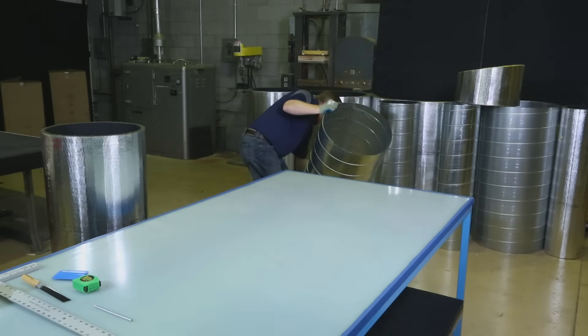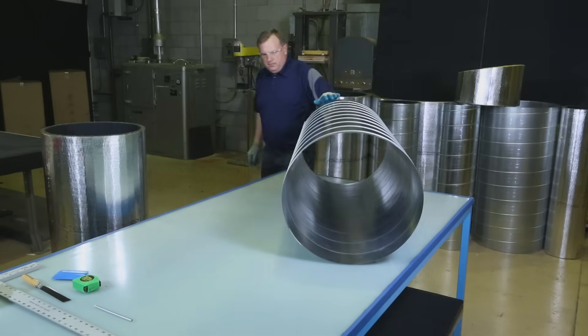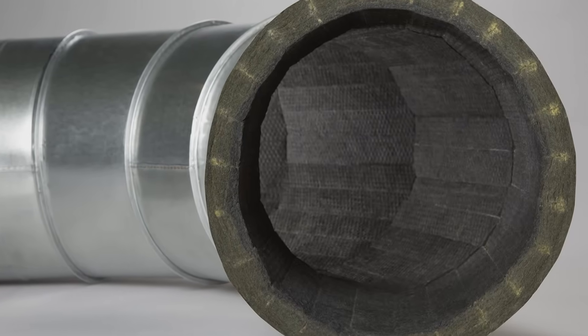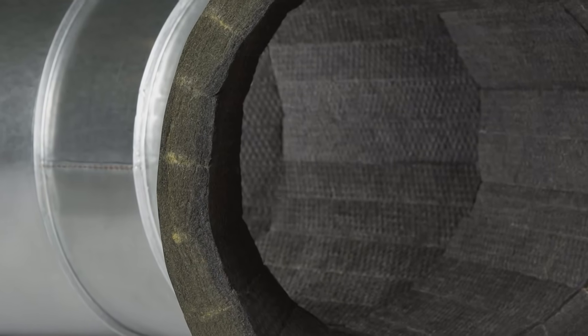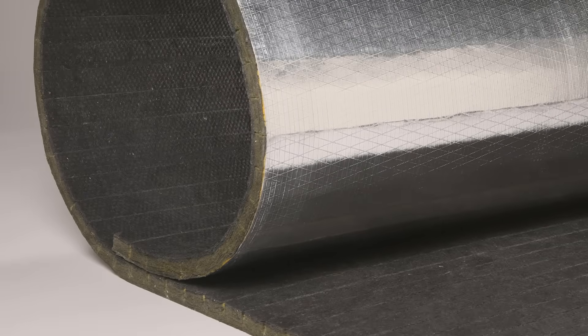The installation labor savings alone are significant, and by eliminating the need for a perforated metal inner core, you can cut metal fabrication time and metal cost by up to 50%. The airstream surface and section ends are covered with JM's proprietary Permacoat coating, which contains an EPA registered antimicrobial agent. The curved surface comes together in a nice tight joint with no gaps or lifting, and no possibility of fiber shedding. Spiracoustic Plus typically requires no pinning or adhesive application in straight supply ductwork, with only minimal pinning and gluing in certain fitting applications.